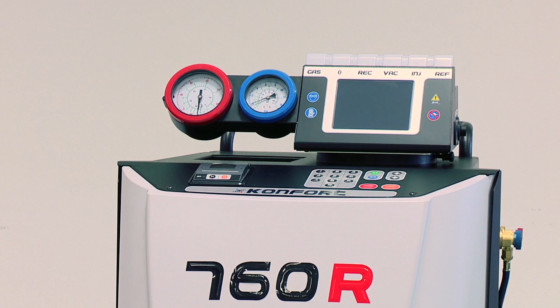This brings us to the key point of discussion. The best practice for regular AC maintenance is only one, and it is very simple. Recover at least 95% of the refrigerant from the AC system. Recover and drain the smallest quantity of oil possible. Create a deep and long enough vacuum in order to remove all the contamination with air and humidity. Fill the AC system with the same amount of oil previously removed. Perform the refill phase with the proper amount of refrigerant.